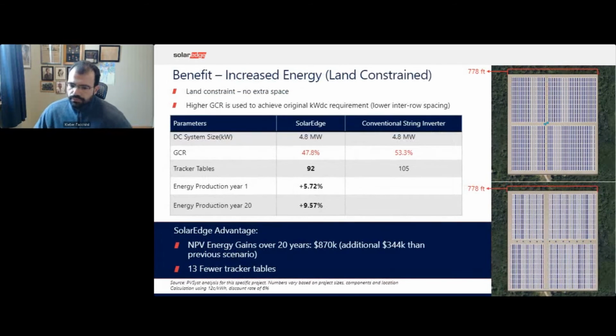Now, however, when we showed this to a customer, they said, Kleber, look, land is not always available for us to put extra tables. So because land is not always available for tracker tables, we ran the case when more land is not available for the additional tracker tables within a conventional string inverter system for a set kilowatt. Again, the system with conventional string inverters needs to use 13 more tracker tables than the system with the SC330K. And to fit these additional 13 tracker tables in the same plot of land, the designer needs to increase the ground coverage ratio, GCR, which shortens inter-row spacing, potentially creating inter-row shading. So you need to make the inter-row spacing shorter so that you can fit all of the panels.